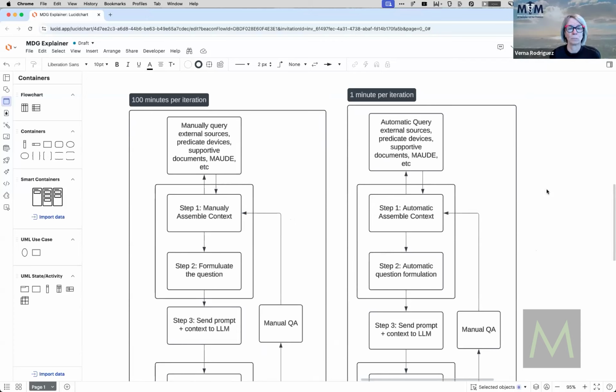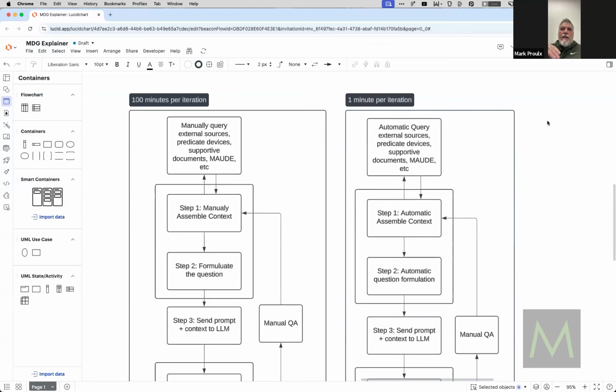That was what I was saying about the whole DHF thing, is that you have an entirety of activities from beginning to end that include the trace matrix, GSPRs and post-market surveillance and risk management and all these other documents, and design requirements and inputs and outputs and verifications and validations. You have a trace matrix across all of this. If that were a big program that included this one we're talking about right here as a line item that did the search, you can start at the top and say, I want to build a certain product. Let me put that in.